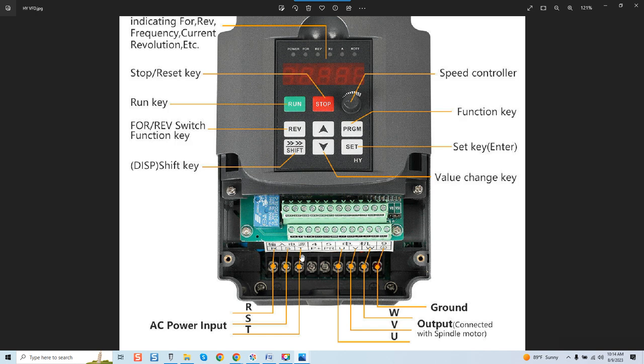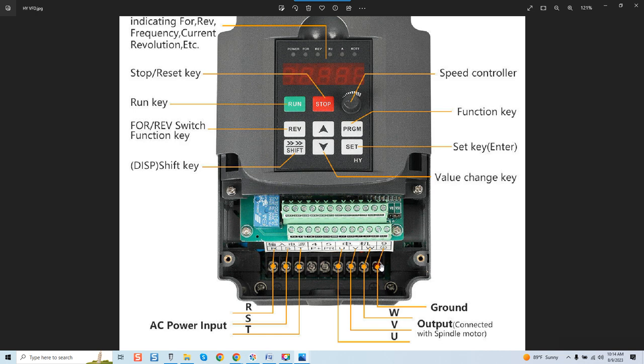Okay I'm hooking up a 220 VFD. Where do I put the ground? Well we know the ground over here you have one ground so I'll say it again. You're going to connect your AC ground from this side over here. Now we all know you have only one terminal here for ground. That means you technically should split this with a terminal splitter which is why I designed my VFD ground splitter kit.